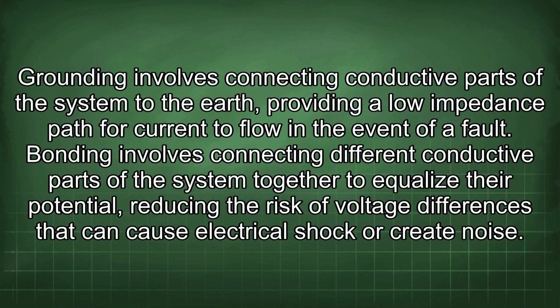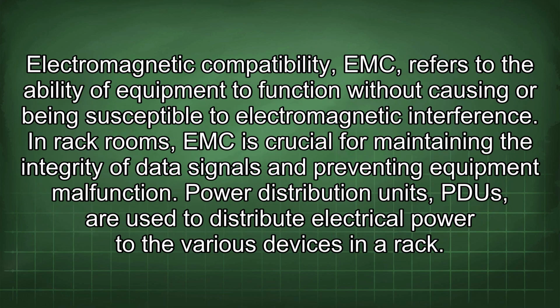Bonding involves connecting different conductive parts of the system together to equalize their potential, reducing the risk of voltage differences that can cause electrical shock or create noise. Electromagnetic compatibility, EMC, refers to the ability of equipment to function without causing or being susceptible to electromagnetic interference. In rack rooms, EMC is crucial for maintaining the integrity of data signals and preventing equipment malfunction.